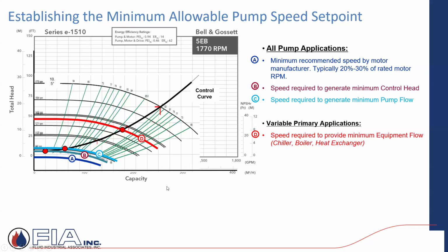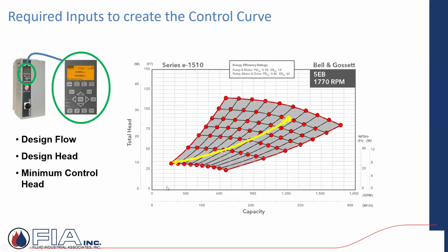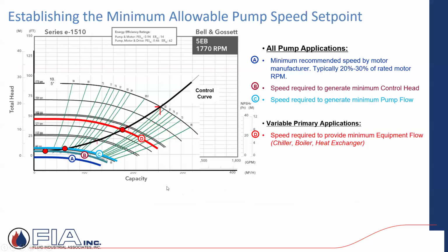Variable primary speed required. Hey, if I have no primary secondary, so I have variable flow through both my chillers or boilers and my terminal units, maybe that minimum flow requirement is going to be my equipment. My chiller manufacturer says, hey, don't go below X. I can vary, but don't go below a certain minimum threshold. So any one of these four could be what establishes that minimum allowable pump speed when you're setting these conditions, or setting the parameters within the drive.